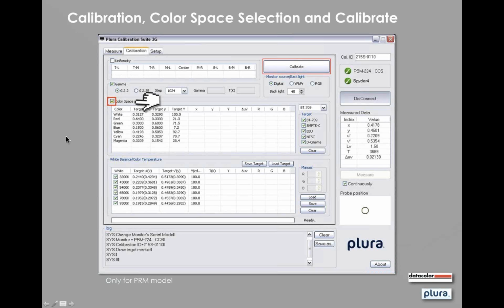Now, on the PBM224, I'm going to ask David Philpott to step in a moment. On the PRM model, one would enable the color space, and you would see all of these be populated. On the PBM224, you would not enable the color space setting. David, any other comments on this? Yeah. For the most part, we have one model that's a Plura reference model, or a PRM. There are 3 different sizes of that: a 17, a 24, and a 32. And that's really the only models that you would use this color space for. Any of our PBM or SFP or LCM or any of the other models that we have, you would not be using this color space for. It would actually fail during calibration if you selected this. So, okay. And that's all I have.